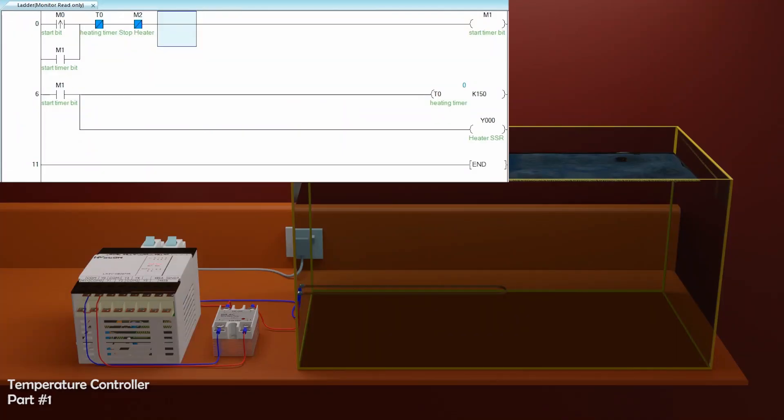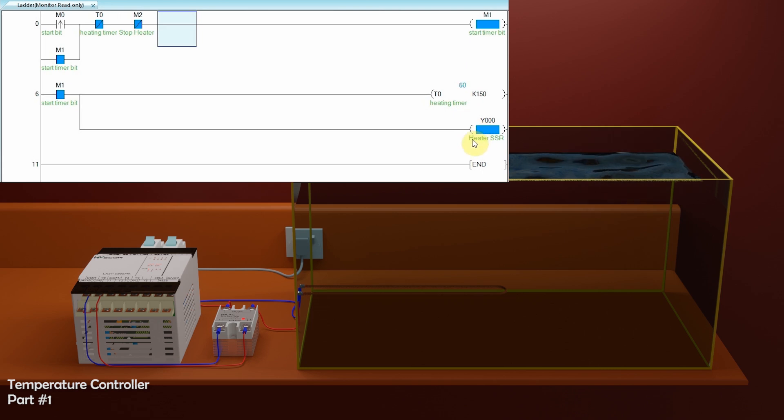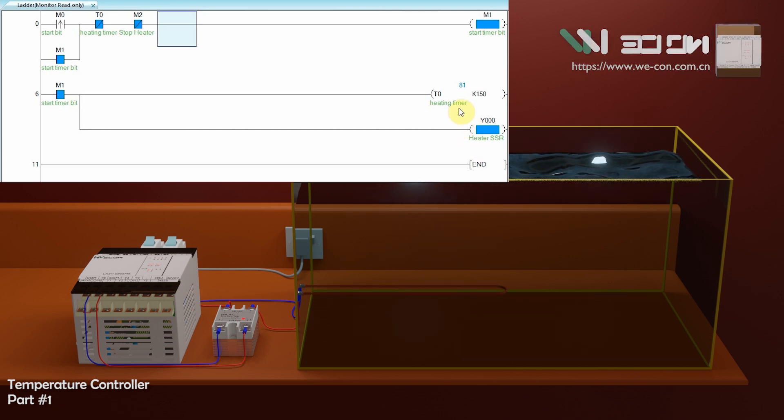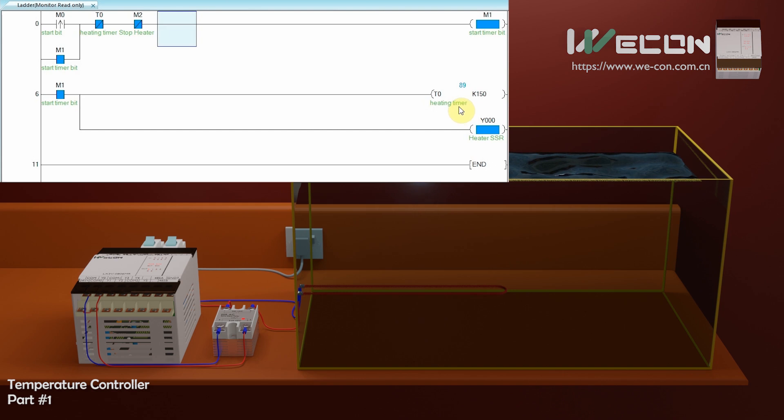As soon as there is a rising edge of start bit M0, the M1 start timer bit gets hold on, and this bit starts the heating timer T0, and in parallel Y0 PLC output turns on, and SSR starts conducting the current.